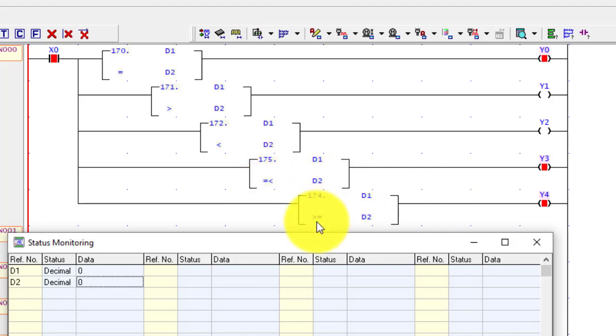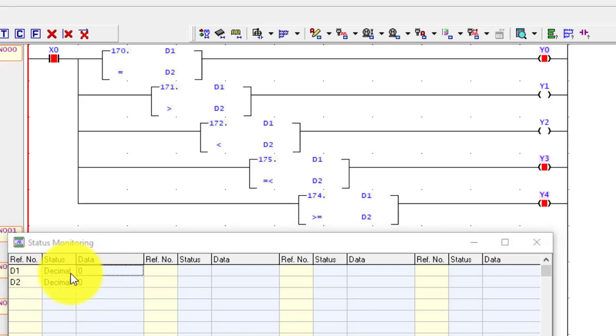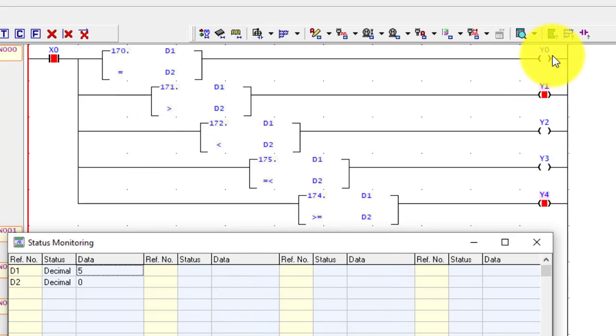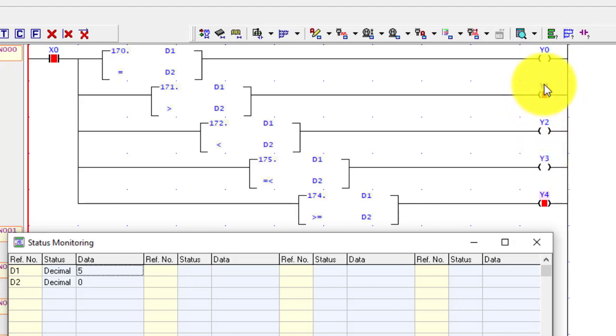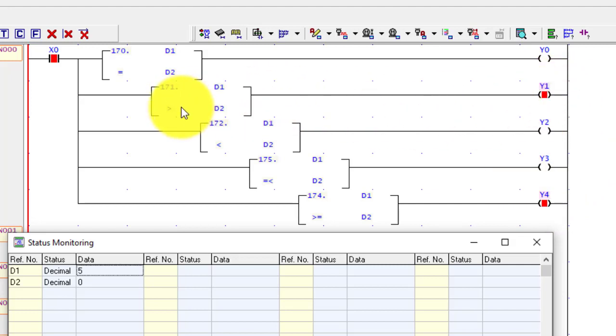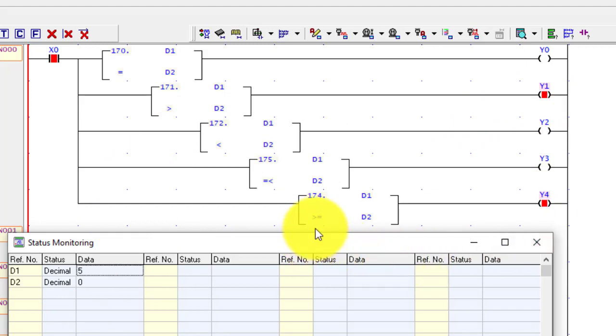I will change the value — I put D1 to 5. Now Y0 is off, Y2 and Y3 are also off. Only Y1 and Y4 are on because Y1 has the greater than command — D1 is greater than D2 — so Y1 is on. And for Y4, greater than or equal: D1 is greater than D2, so Y4 is also on.